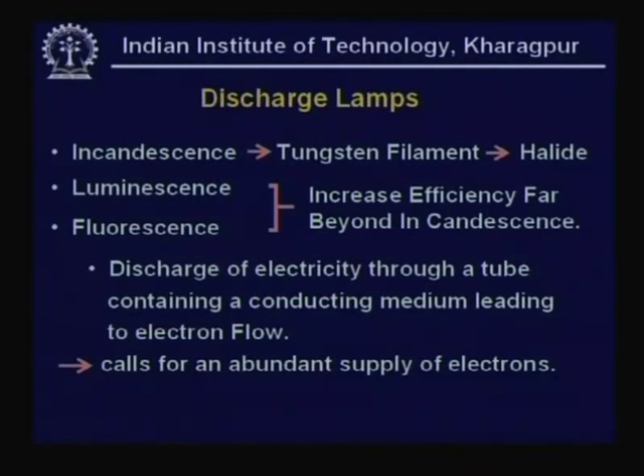We defined light efficacy as lumens per watt of electrical energy input, since most lamps are powered by electrical energy. Tungsten filament and halide lamps fall under incandescence. The next phenomenon employed is luminescence or electroluminescence — radiation obtained by creating a discharge in a gas or vapor by application of an electric field, unlike incandescence where filament material is heated. This allows operation at relatively lower temperatures, which is one reason discharge lamps are more efficient.